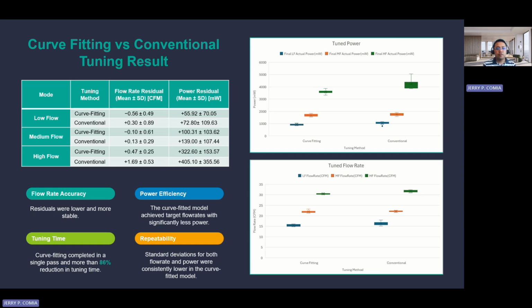This slide compares the curve fitting method and the conventional method. In terms of flow rate accuracy, the curve fitted model produced lower and more stable residuals. In terms of power efficiency, the curve fitting method achieved the target flow rates using less power than the conventional method. In terms of tuning time, curve fitting completed the process in a single predictive pass and reduced tuning time by more than 86%. For repeatability, the curve fitted method had the lower standard deviation in both flow rate and power. Overall, this confirms that curve fitting is more accurate, faster, and more consistent than conventional tuning.